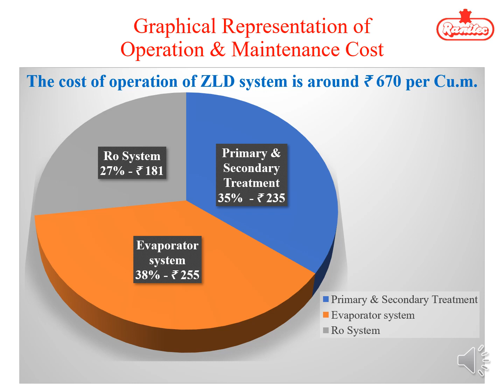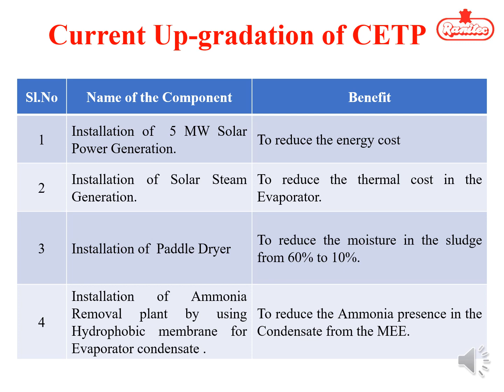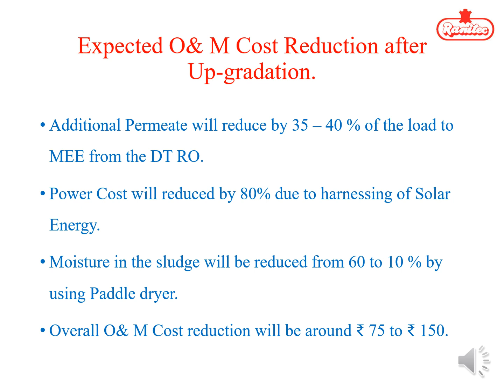Moreover, in order to reduce the operation and maintenance cost of the ZLD system, the CETPs have taken a lot of measures to upgrade the CETP. Some of the components are mentioned here: a solar power generation system of 5 megawatt capacity, solar steam generation, a paddle dryer for reducing moisture in the sludge generated from the primary treatment, and ammonia removal for the condensate from the evaporator. The expected O&M cost reduction after upgradation: additional permeate by disc RO will reduce the load to the MEE by 35 to 40%, and power cost will be reduced by 80% due to harnessing of solar energy. Moisture in the sludge will be reduced from 60 to 10% by using the paddle dryer. Overall O&M cost is expected to be reduced by around 75 to 150 rupees per cubic meter.